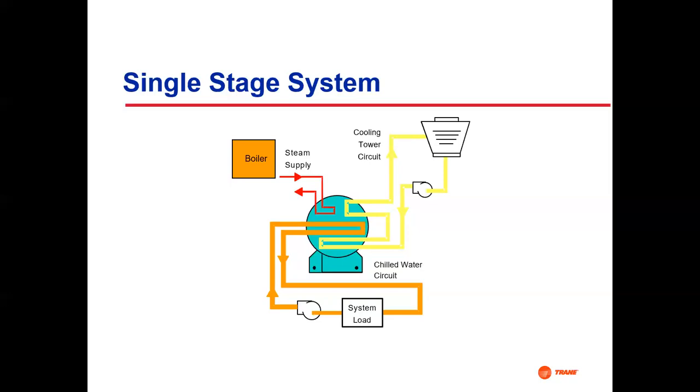Anyway. But this loop is constantly exposed. This cooling tower is open, and it's constantly exposed to the atmosphere. It's constantly picking up oxygen and potato chip wrappers, and Lord knows whatever else gets into it. It's also a very good scrubber. It scrubs the air through it, and all that particulate winds up in the condenser water, this cooling water. Every year they have to close these things down and shovel the mud out of the bottom of that trough down there, because it builds up over time and falls out. And it can fall out all over the place. So these cooling tower loops require a lot of maintenance, a lot of chemical treatment and all that sort of thing. But the chill water loop ought to be good.